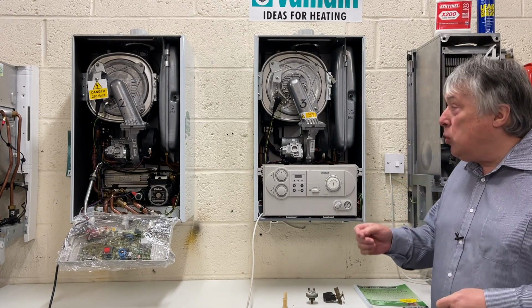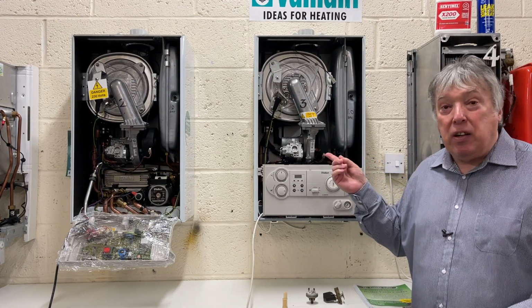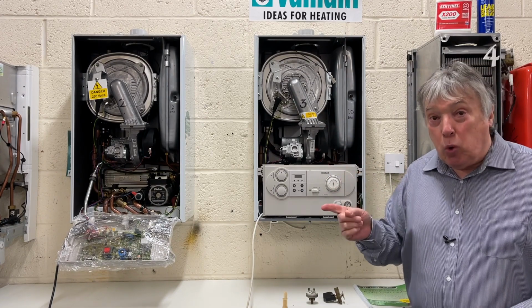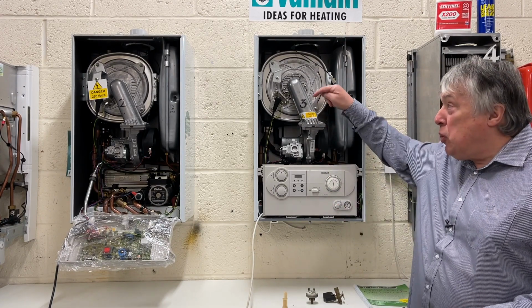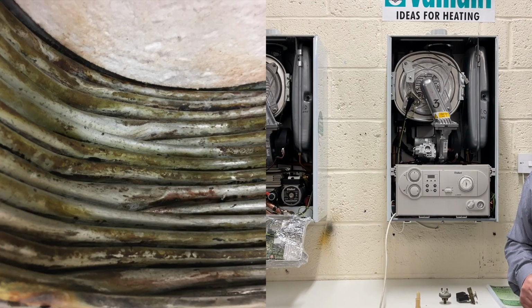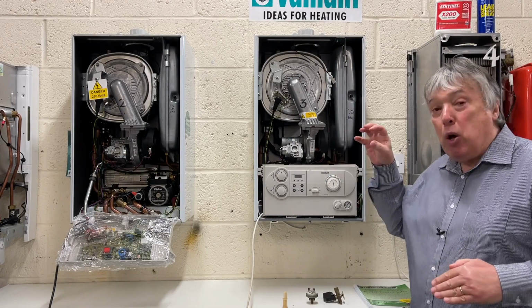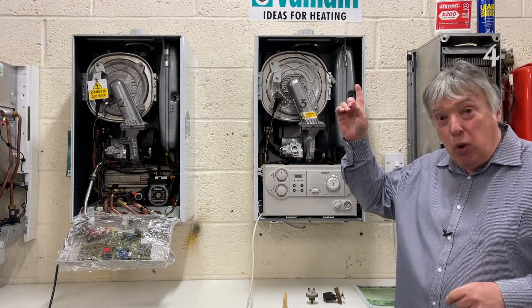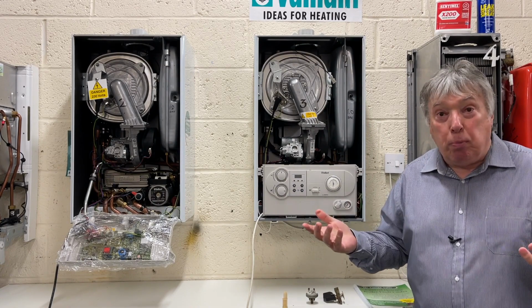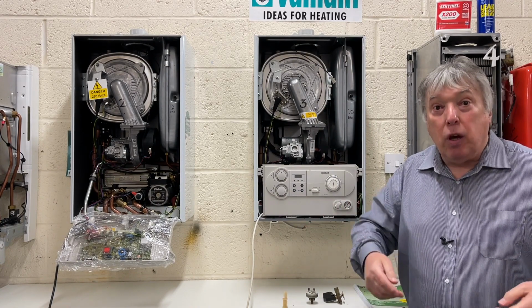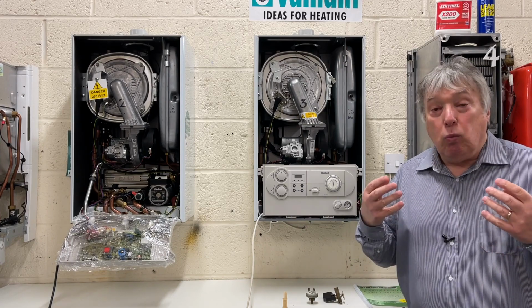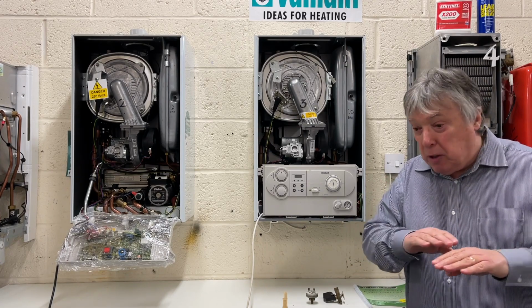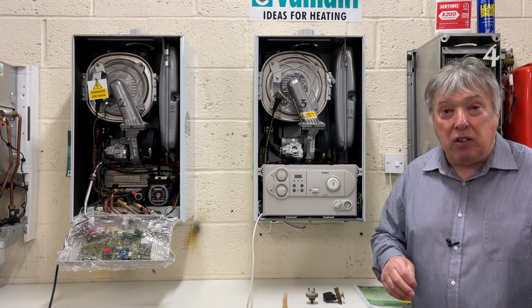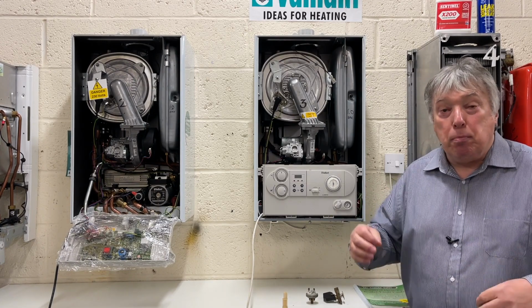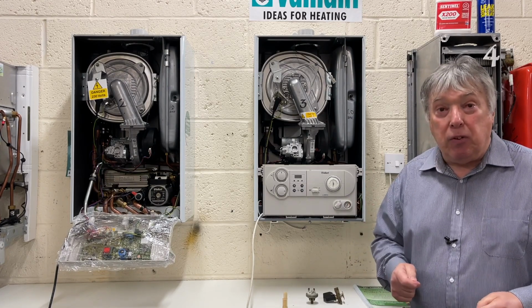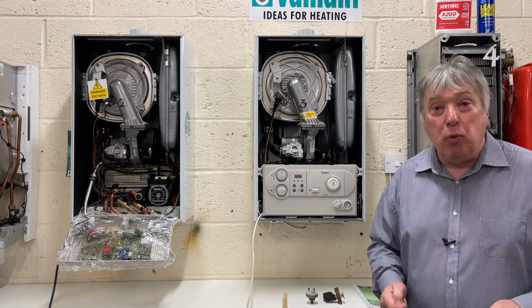So if you have an F code that says the fan, don't just think that the fan is dead or whatever. It could be the flue. It could be the gaps between the heat exchanger coils. If they've blocked up, that fan can't blow through it and go out through the flue. And you'll get an error code, the flue's blocked or the fan's broken. So if you understand what I'm saying, don't just look at one little thing. It's going to be no water, no fan, or lack of gas, whatever. You need to check all the different bits and pieces. So that's why I've made the video, and hopefully you'll improve your diagnostics.